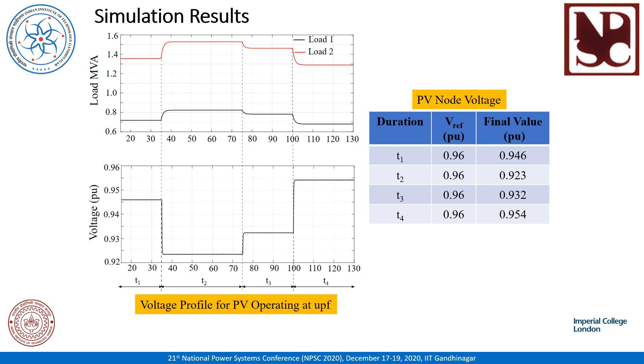To show the advantage, the proposed technique is compared with the conventional Q injection technique and the conventional active power curtailment technique. The loading profile for the two loads is shown in this graph. During the initial phase T1, all the three techniques can successfully regulate the PV node voltage to its reference 0.96 per unit value. However, in the next phase T2, as the load is increased by 25%, the regulation of the load voltage to 0.96 per unit is infeasible for all the three voltage regulation techniques.